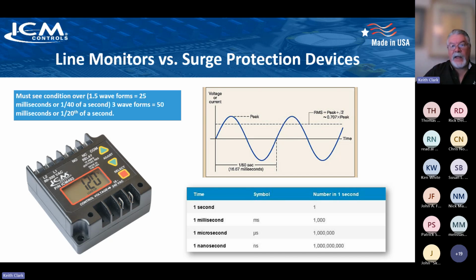You can extend that out if you like. So now it's even a longer period that it's going to look at the sine waves before it decides there's an actual condition and faults. But it must see a minimum of 1.5 waveforms or 25 milliseconds. So you see, line monitors are now monitoring things in milliseconds as opposed to nanoseconds, a billionth of a second, for the surge devices. Now we're looking at things in milliseconds, a 1,000th of a second. So you can see it's a longer period of time that this thing wants to see those waveforms, and it wants to know that there's a condition.